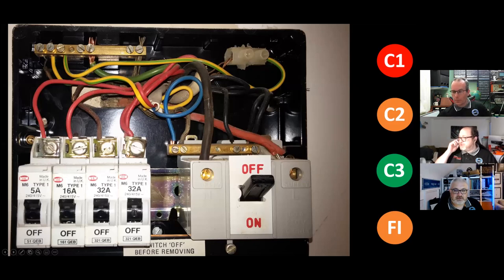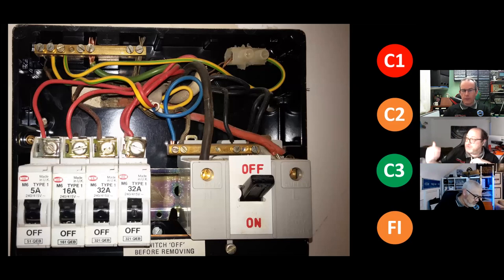Is this one of yours, John? What did you do? Did you do a C2 here? I think this was a C2 because from memory it only supplied a single socket, so there wasn't any risk of actually overloading it. But you're now thinking about other stresses that this will then have to take. That makes sense. Okay, yeah.